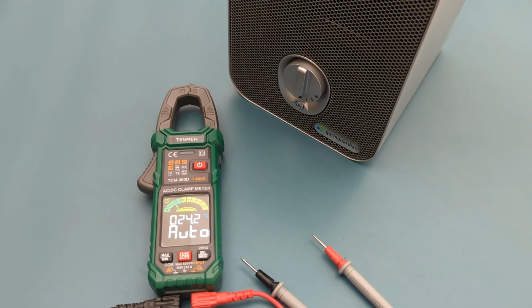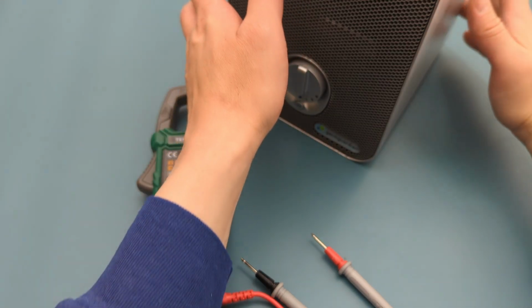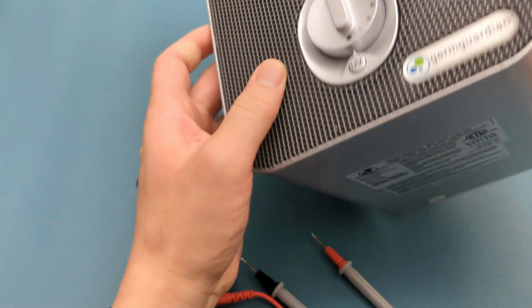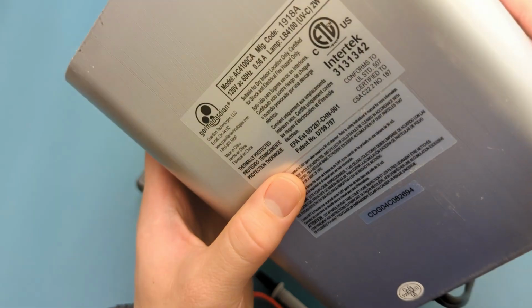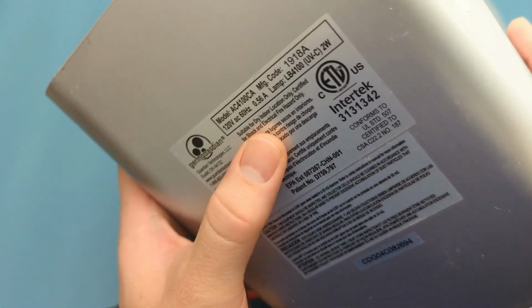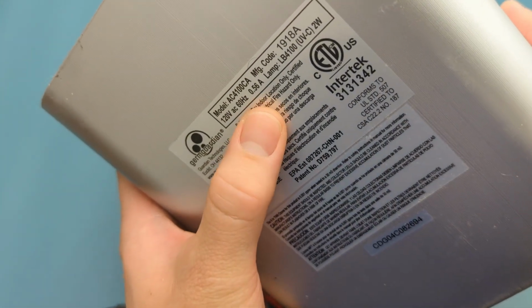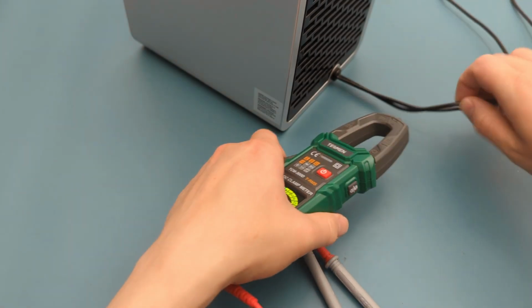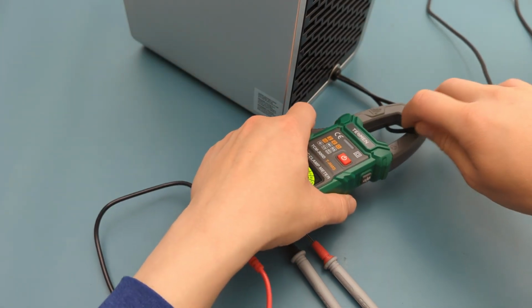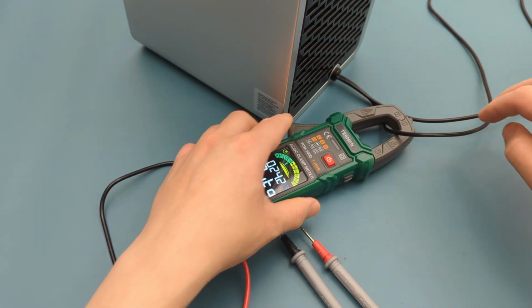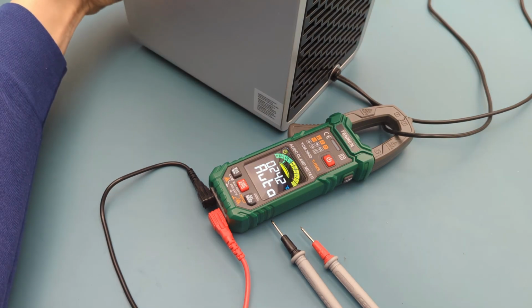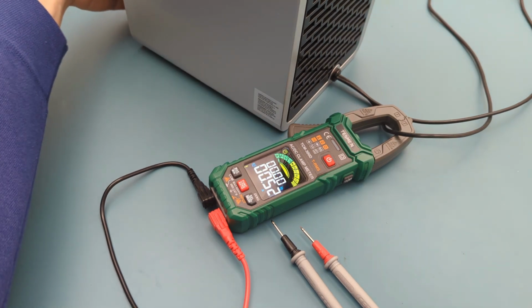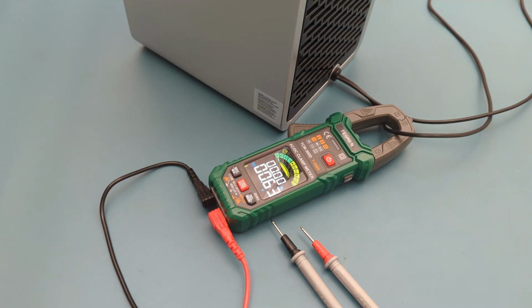The next test is to do the current measurement. I have a portable air filter that connects directly to a wall outlet. According to the specifications, it needs an input of 120 volts and 0.56 amps. Press the trigger and slide the power cable into the clamp. No amps are showing yet because I haven't turned on the filter. Let me turn on the air filter. When I turn on the air filter, the reading shows around 0.6 amps.